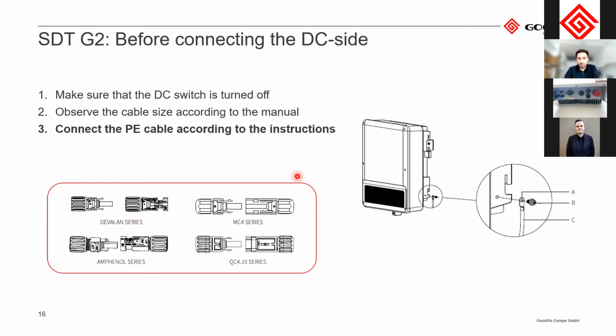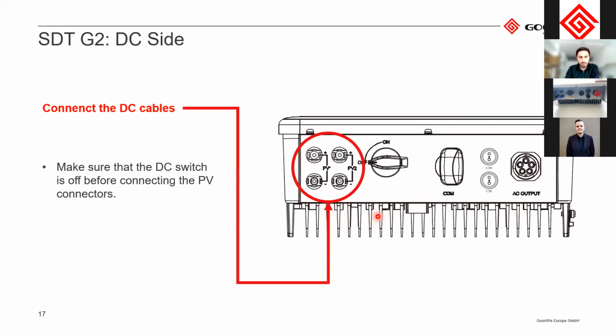For the DC output, before you do that, on the side of the inverter, there is a separate ground or earth cable that you need to connect. Please do that before you connect any other DC cables to the inverter. Also make sure that the DC switch underneath is turned off before you connect any cables. And then also please observe the correct cable sizes for the PV inputs. And then you can just connect the PV inputs here. And again, make sure that this DC switch here is turned off.